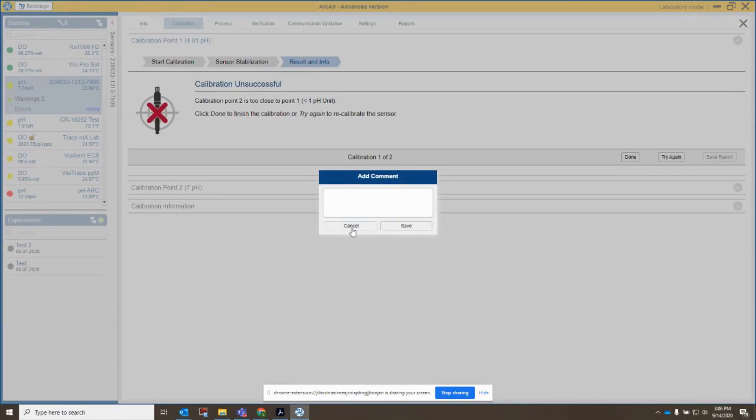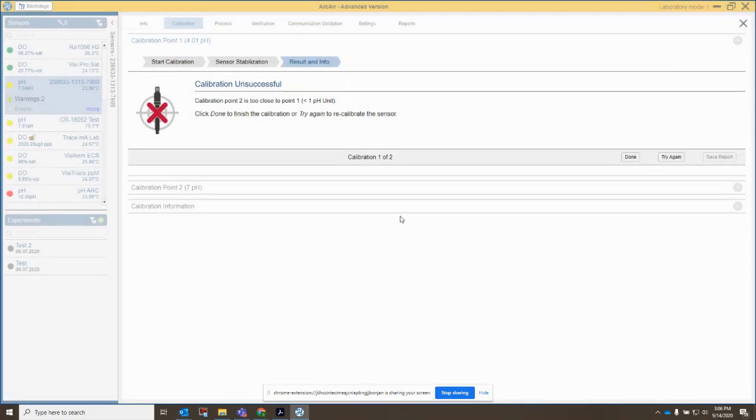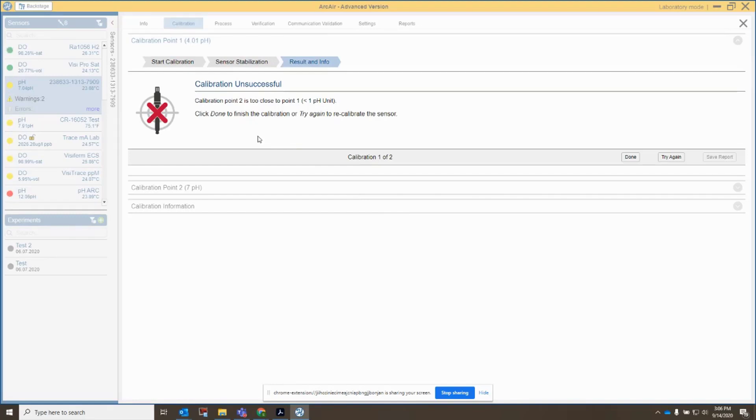It says add comment. It says calibration point 2 is too close to point 1, less than one pH unit. So I failed my calibration, and that's because I'm trying to calibrate at a point that is exactly the same as my second point, and so that's a problem. You need to have at least a difference of one pH unit to do a proper calibration.